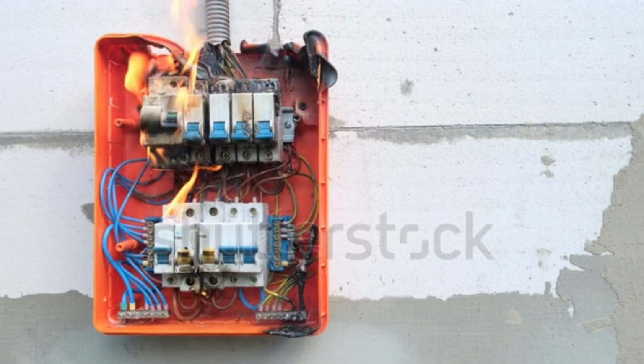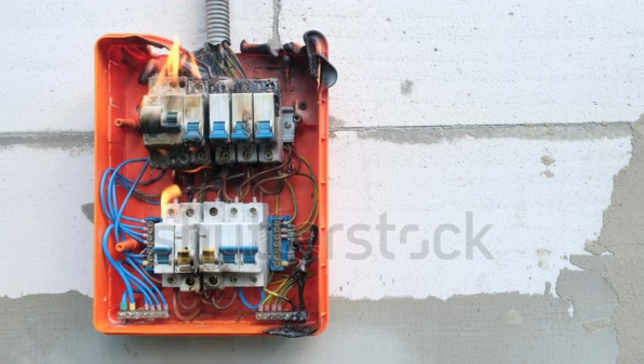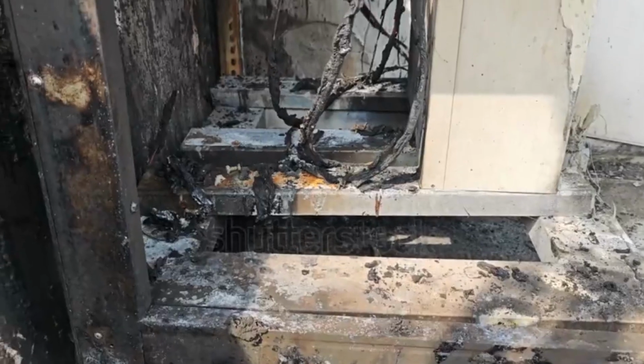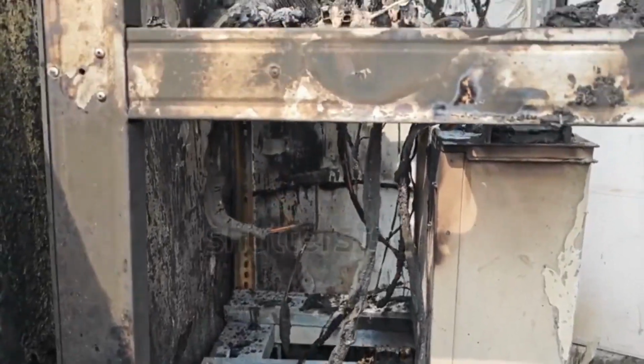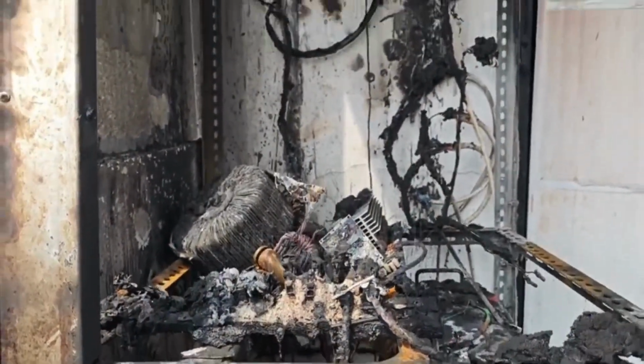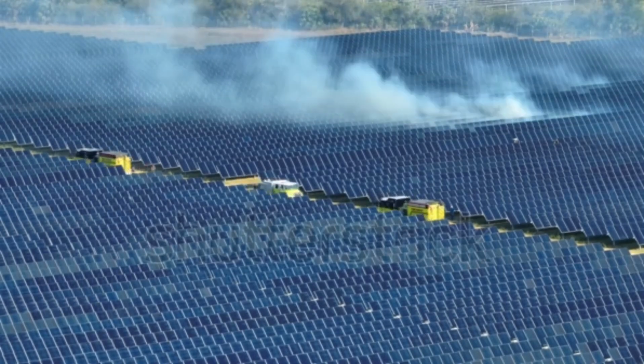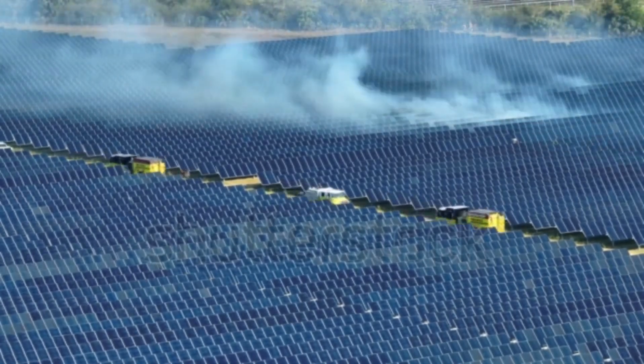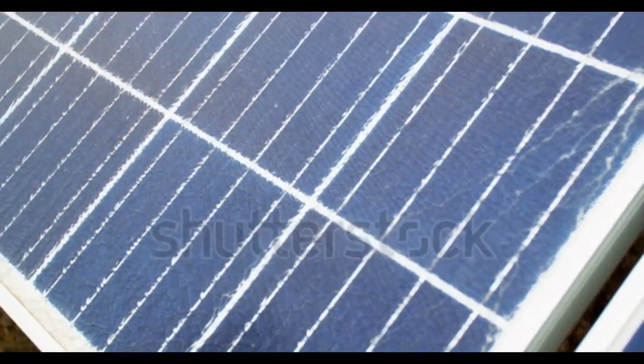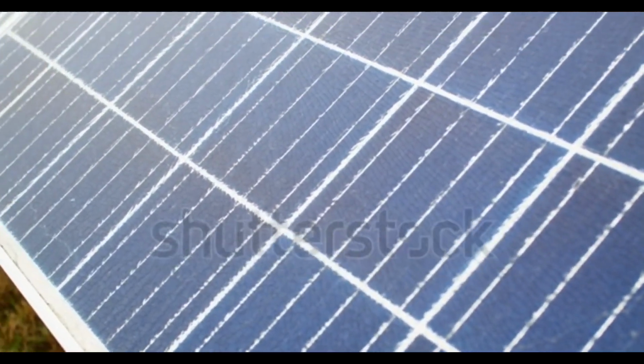4. Environmental factors. Extreme weather events. Hailstorms, strong winds, lightning strikes, and floods can physically damage solar panels or other components of a solar plant. In extreme cases, panels can crack, mounts can be damaged, or inverters can be flooded. Dust, dirt, and pollution. Dust and soiling can accumulate on the surface of solar panels, reducing the amount of sunlight reaching the solar cells. This can decrease energy production by as much as 20–25% if left uncleaned for extended periods.